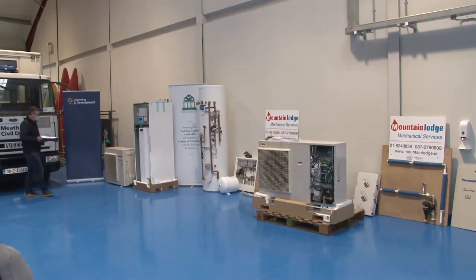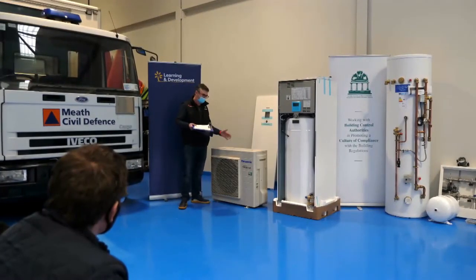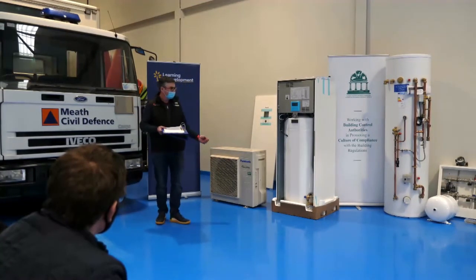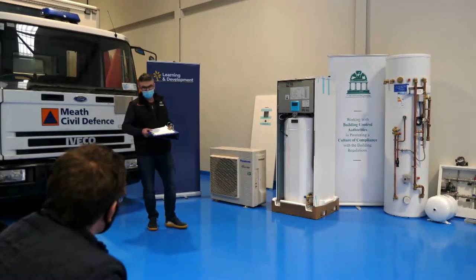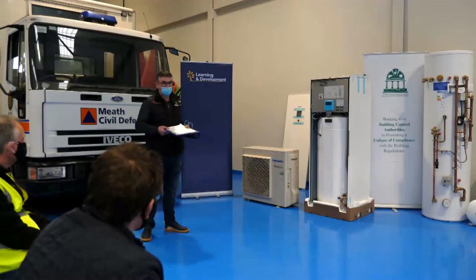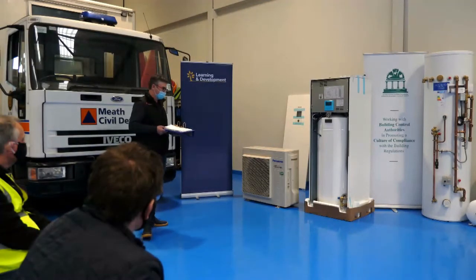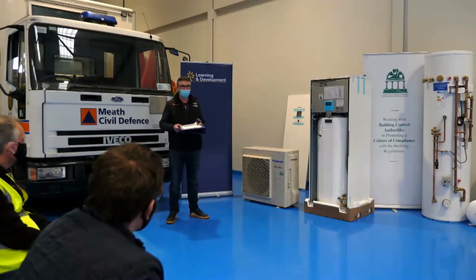So again, outside you're looking for the electrical isolator and fridge pipework. Again, it should be disappearing quite. You shouldn't see much exposed pipework. If it's a little bit of distance away, if you come out to a site and you find that it's 5-6 meters away from the house, you just have to know how that pipework gets back into the house.